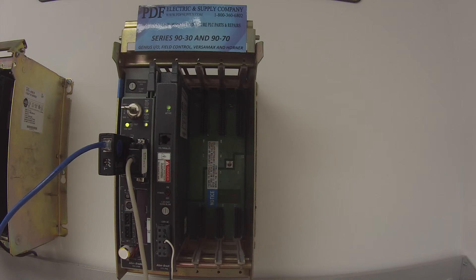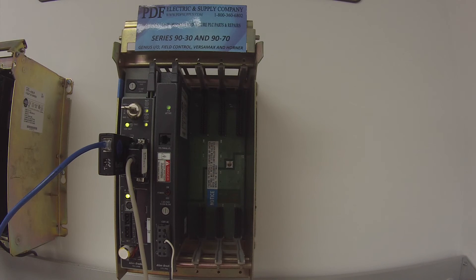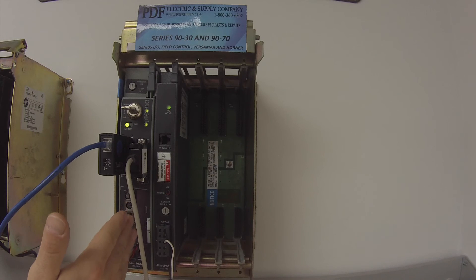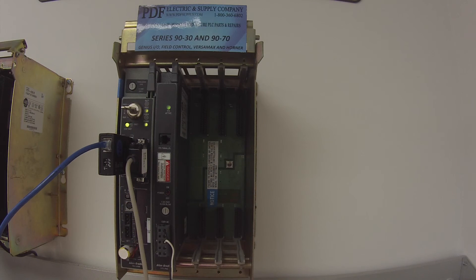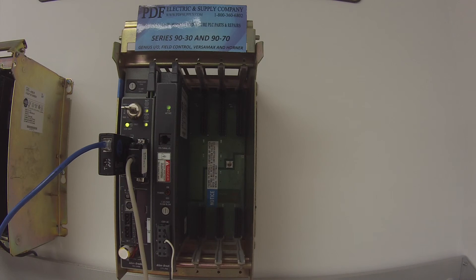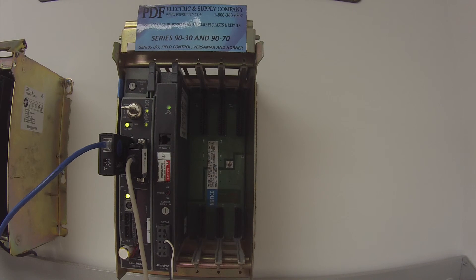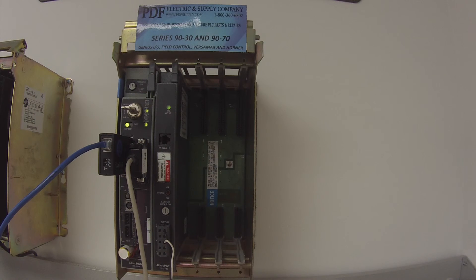Okay. What you're waiting for here is you're wanting a response from the processor. It should ping it four times and give you information on how quickly it responded to that and what the speed is in which it's communicating. As long as you get four clear responses, then the ethernet card is working properly.